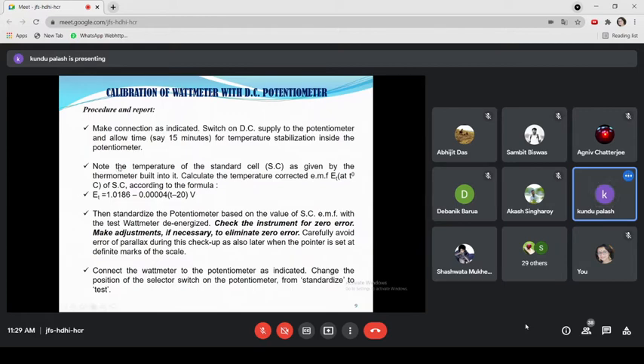Now the standardization process. In the standardization process, the standard cell is used. The standard cell here is either a battery or a Weston cell, the value of which depends on the room temperature of the laboratory. So day to day it will vary. Otherwise, at a room temperature of 20 degrees, the value is 1.0186. If the temperature increases, the standard voltage of the standard cell will decrease. That's why there is a need to note down the temperature using the thermometer and calculate the value of the standard cell corrected at the room temperature in volts. So these must be less than 1.0186.